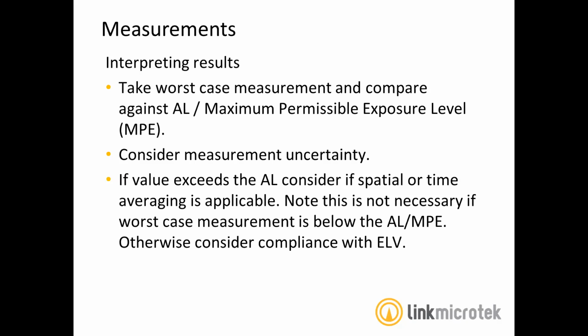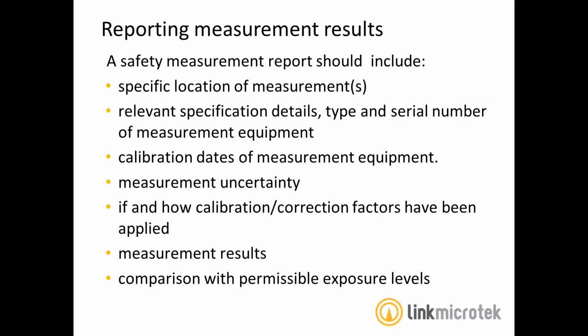So, in terms of interpreting results, take your worst case measurements and compare against the action level or the maximum permissible exposure level. Consider your measurement uncertainty, and if the value exceeds the action level, then consider whether spatial or time averaging is applicable. It's not necessary if your worst case measurement is below the action level, but sometimes you might want to apply it, particularly time averaging for a signal that isn't present all the time. You don't often need to get into it, but we're happy to advise on that.